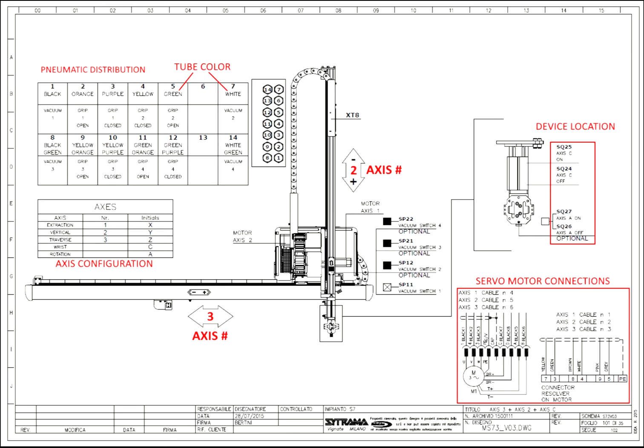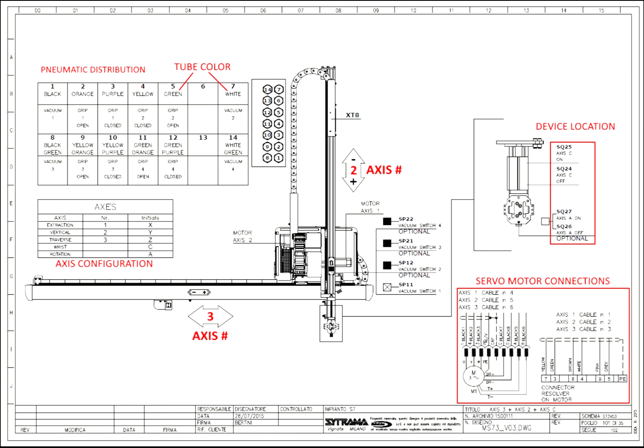Also in our prints you'll notice that we have our pneumatic distribution pages. These pages will tell you what color code the line is. You'll notice if you look at any of your lines they've all got a little rubber coating on them that has a specific color. That is what they're trying to show you in these prints. Once again it shows your axis configuration. They point out what axis is what. Your up and down axis here is axis 2. Your transverse axis is axis 3. And it shows you a couple things about your servo motor connection and device locations.